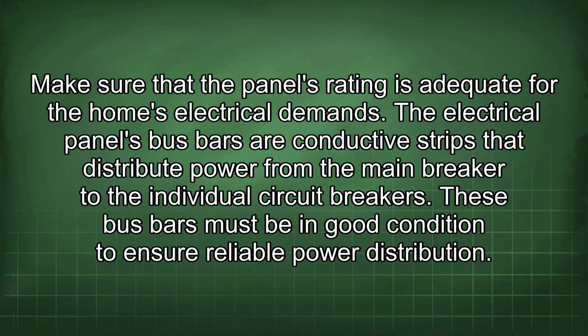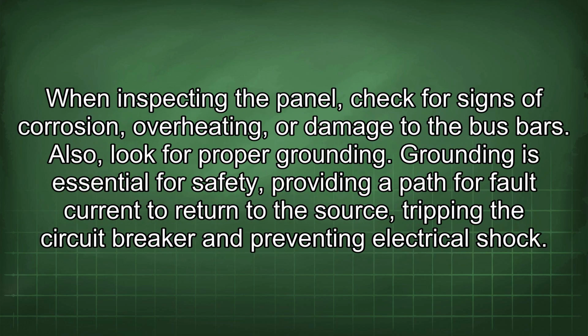The electrical panel's busbars are conductive strips that distribute power from the main breaker to the individual circuit breakers. These busbars must be in good condition to ensure reliable power distribution. When inspecting the panel, check for signs of corrosion, overheating, or damage to the busbars. Also, look for proper grounding. Grounding is essential for safety, providing a path for fault current to return to the source, tripping the circuit breaker and preventing electrical shock.